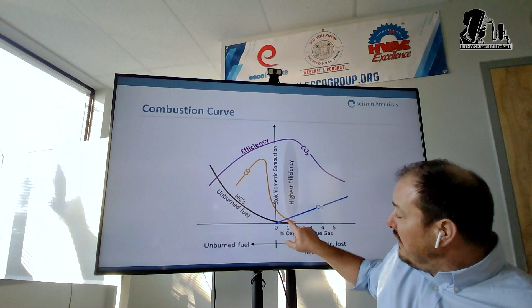But if you notice, where my little curve is for CO in that shaded area is very small, and that means it's 100 ppm to 0. So it's okay to have some CO. But if I get my oxygen and my CO in this range, my CO2 will be at its peak.